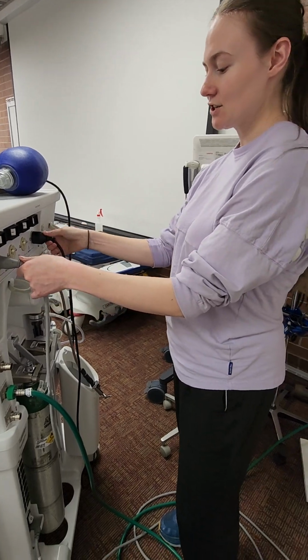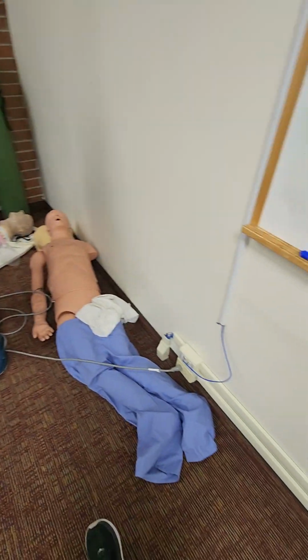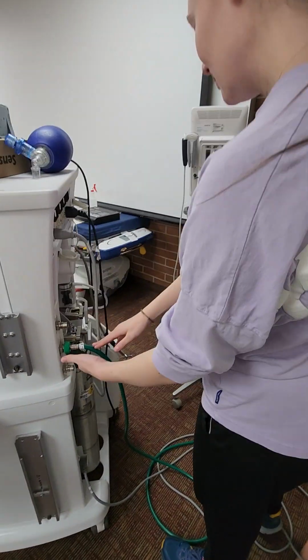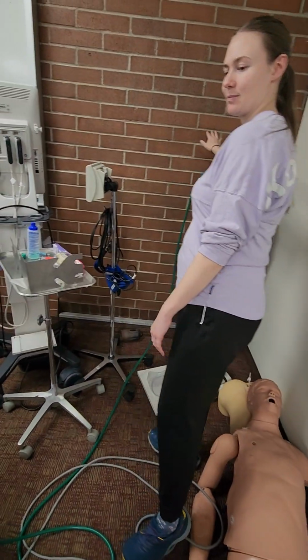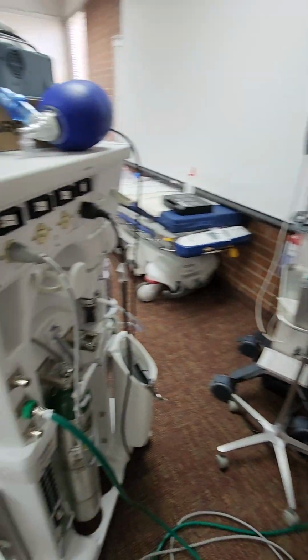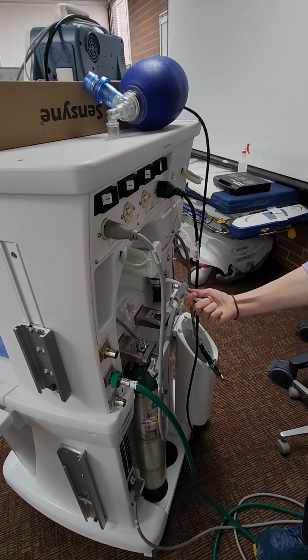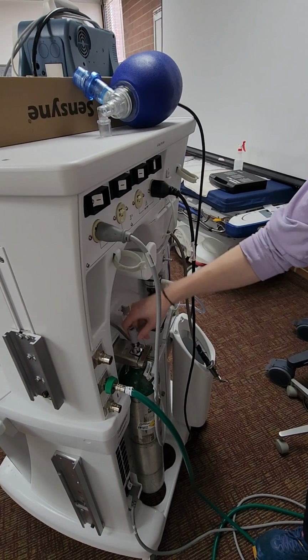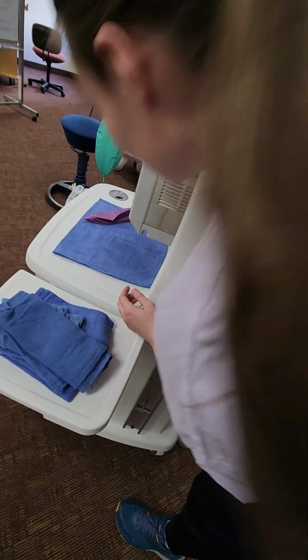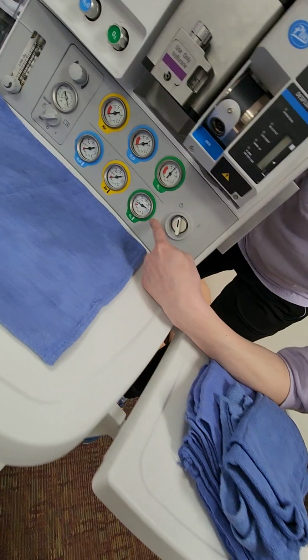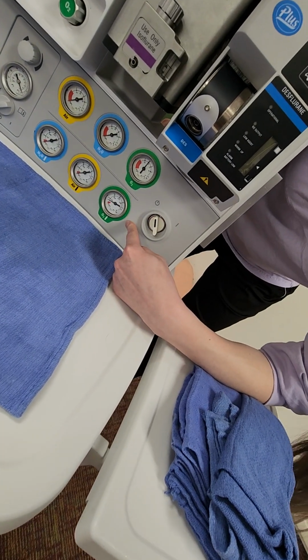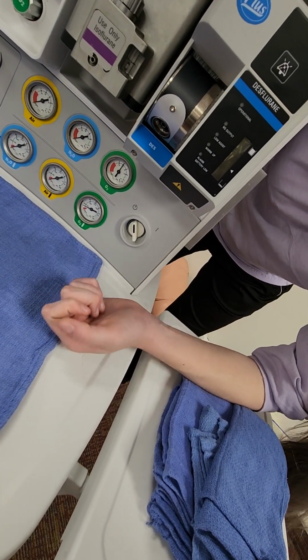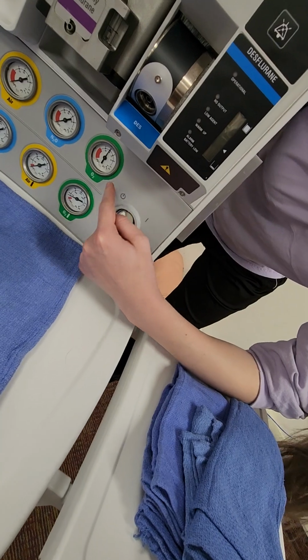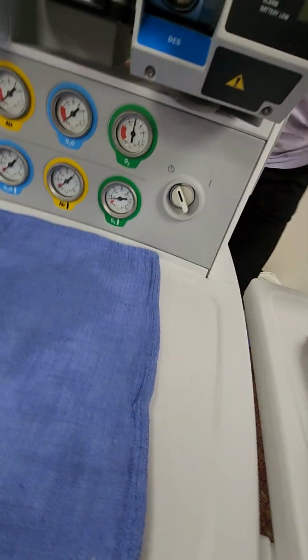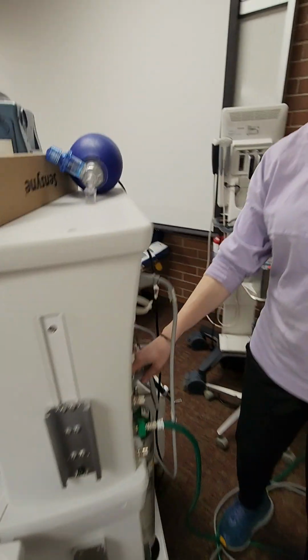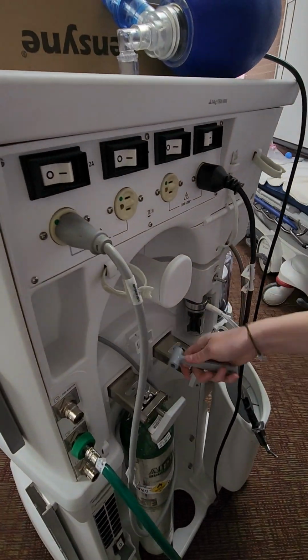Then you want to make sure electricity is connected to the wall, your machine is connected to electricity. You want to make sure your pipeline pressure is connected to the wall pressure, so verify this tube is all connected the right way. The last thing you'll do is you'll take your oxygen key, crack your oxygen, lean over here, double check on this valve that it's above 1,000 psi. If it's lower than 1,000 psi for your tank, you need to go replace it. You'll also look at this and you'll make sure that your pipeline pressure is 50. Then you'll come back over here and close it because this is your emergency oxygen.